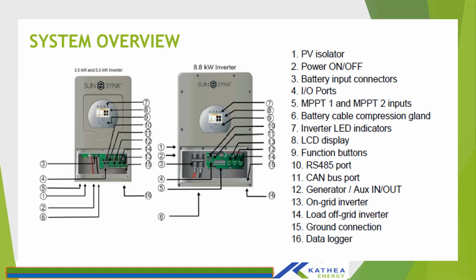You see, the problem that bothers me, Brian, if you say we need to follow that, if the live and neutral are swapped around on the output side, then my live actually becomes a neutral, which means my neutrals are being fed through the circuit breakers, and my neutral terminal is actually becoming live, which to me is obviously not good practice.